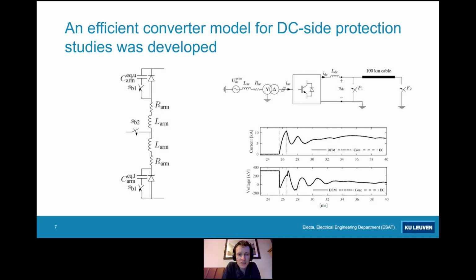With respect to the fault analysis, what we needed was actually an efficient model of the converter. The main source of fault currents is actually the HVDC converter, so coming from the AC side. Now, such a power electronic converter contains a lot of switches and is controlled by a lot of complex control loops. And this makes it very inefficient in a time domain simulation. Reduced order models were developed, but the main focus for these models was on control interactions and not so much on the protection itself.